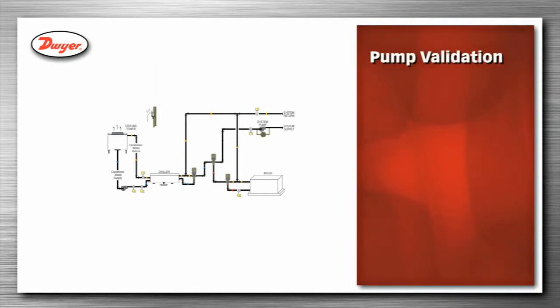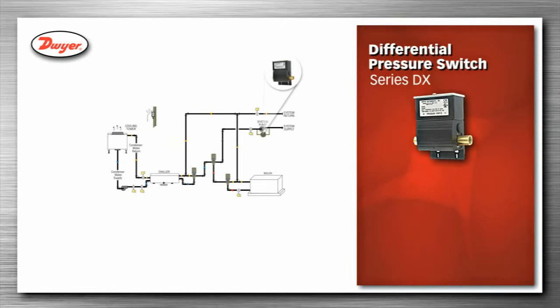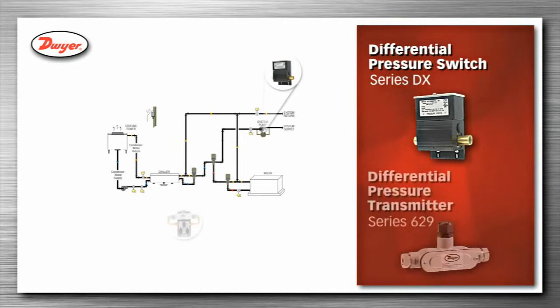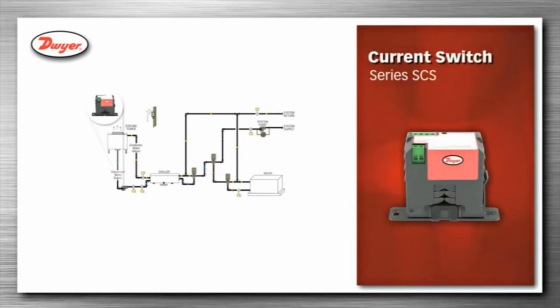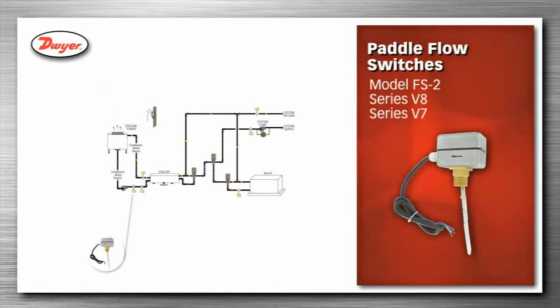Dwyer offers several products that can be used for pump validation, proving that the pump is operating and there is water flow. A differential pressure switch, Series DX, or a differential pressure transmitter, Series 629, can be used by monitoring the differential pressure between upstream and downstream of the pump. Series SCS current switch can be used by monitoring the current usage of the pump. Paddle flow switches, including our model FS-2 Series V8 or Series V7, can be used by monitoring the water flow exiting the pump.